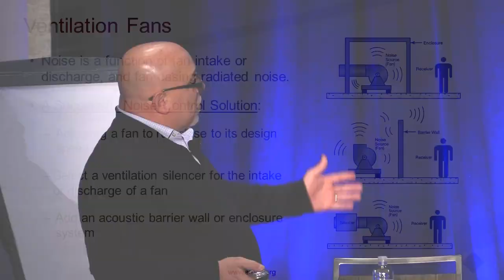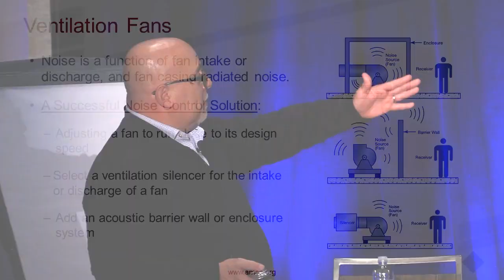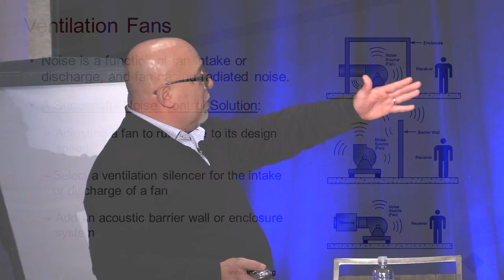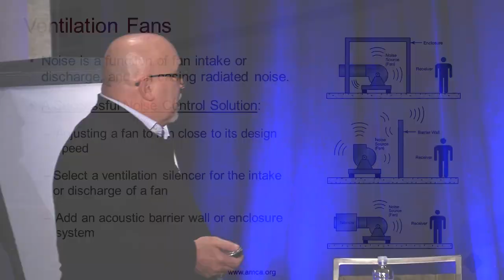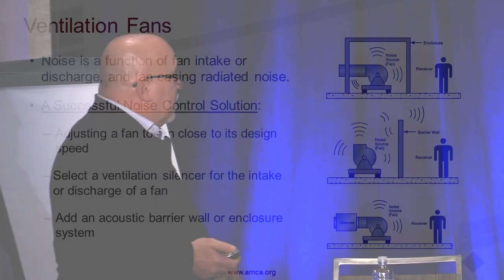You can also sometimes just put a barrier wall around an equipment yard or a fan to control noise, and you can do analyses to determine whether you're in the shadow zone close to it or whether you're getting a reflective up and over diffraction. You can put a silencer on the discharge of a fan, as you see down at the bottom, or on the intake. Sometimes you might have to do the top one and the bottom one, or both of these, the middle and the bottom. It's just a lot of things you can do.